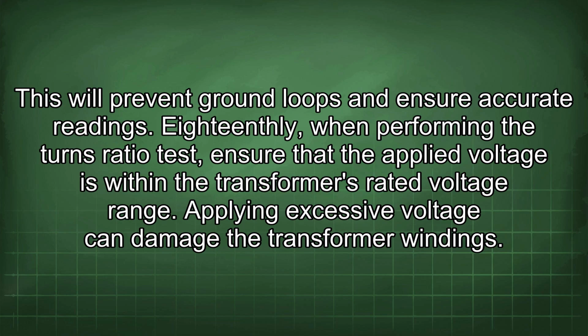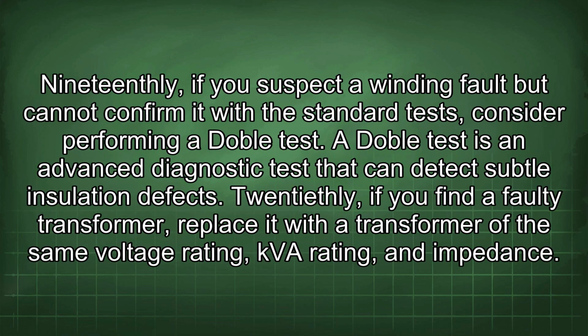18thly, when performing the turns ratio test, ensure that the applied voltage is within the transformer's rated voltage range. Applying excessive voltage can damage the transformer windings. 19thly, if you suspect a winding fault but cannot confirm it with the standard tests, consider performing a Doble test. A Doble test is an advanced diagnostic test that can detect subtle insulation defects.